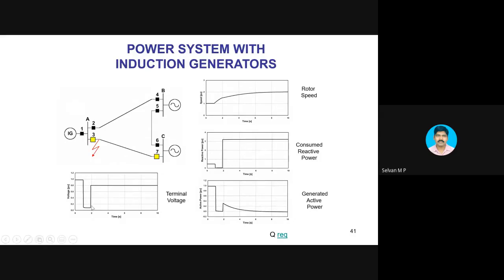It cannot provide reactive power to set up the magnetic flux, so there is no magnetic flux available. When there is no magnetic flux available, the electromagnetic torque becomes zero. So there is a torque mismatch between the mechanical torque and the electromagnetic torque. Because of this mismatch, the rotor gets accelerated and the rotor speed increases continuously.